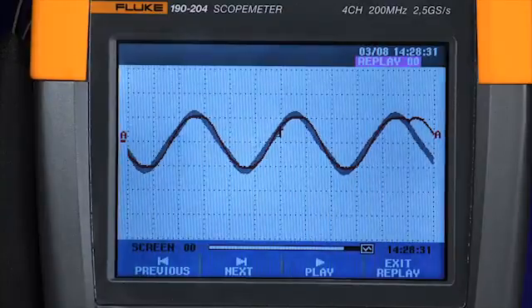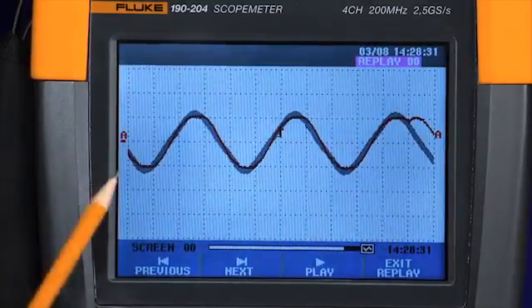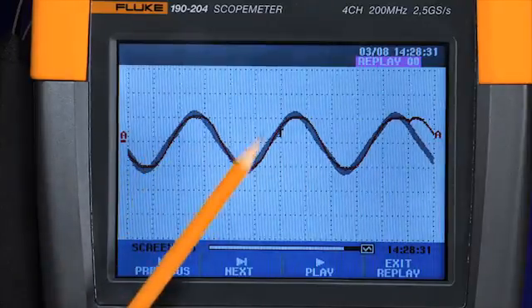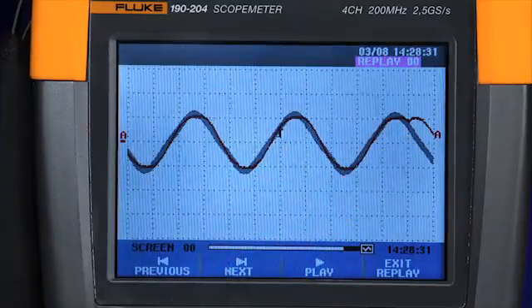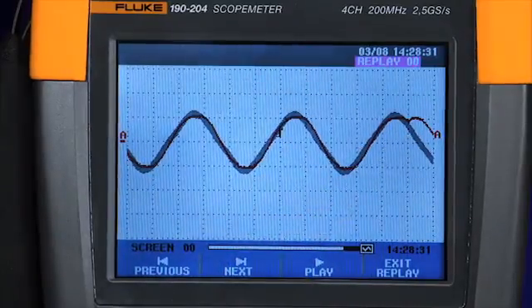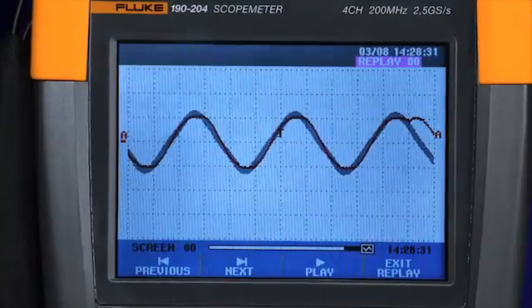Immediately, you can see the gray envelope overlaid with the waveform trace the scope has captured. In this test, you can see clearly that at the end of the cycle, the waveform exceeded the two pixel tolerance window. You can also go through each of the memories and inspect every waveform looking for such anomalies.